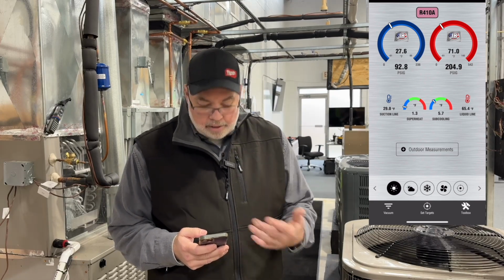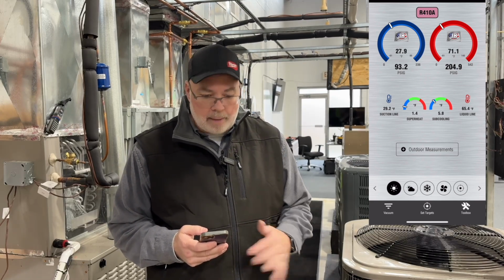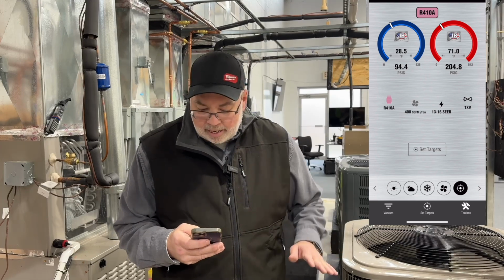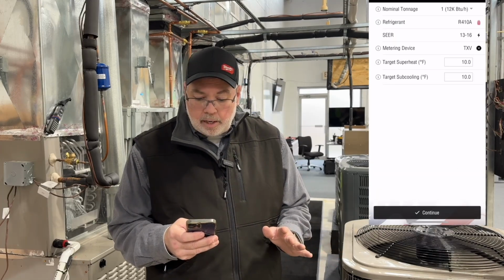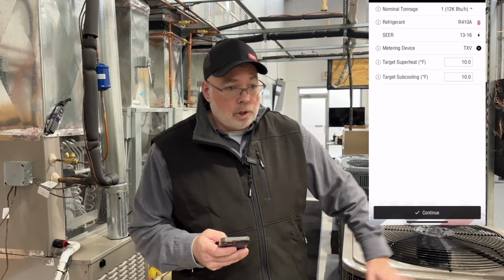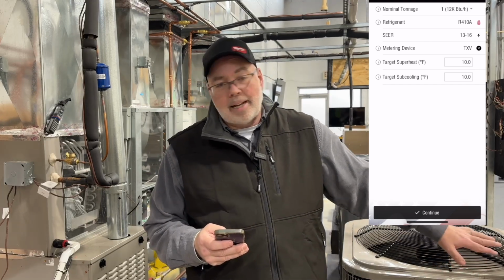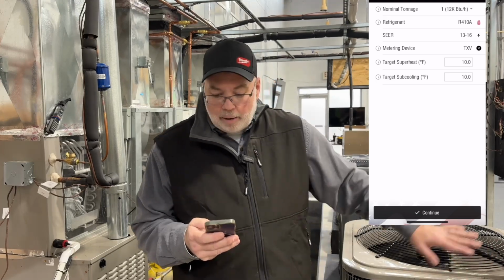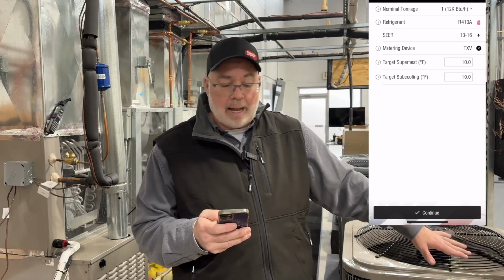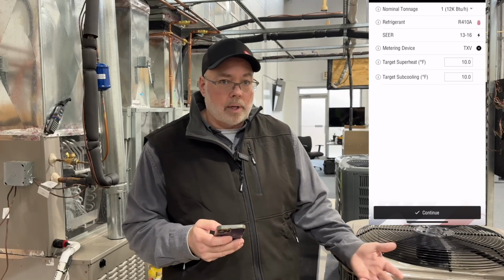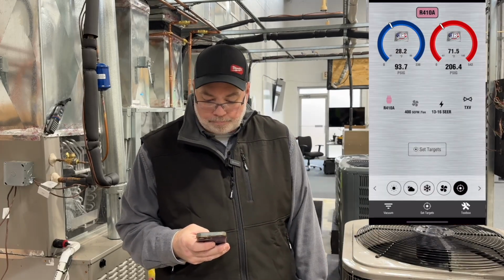Now, what we're looking at now is our JB Go V2 app. It calculates superheat and subcool automatically for you. We told it what refrigerant we have, and we profiled the system. Now, we can actually go and set our targets. And here is where we're going to enter what our superheat and our subcool targets should be. So if I go over here to the outdoor unit and it says I need a subcool of 8, then I would enter under this target subcool 8. That way it'll tell me whether I'm at my target or not.